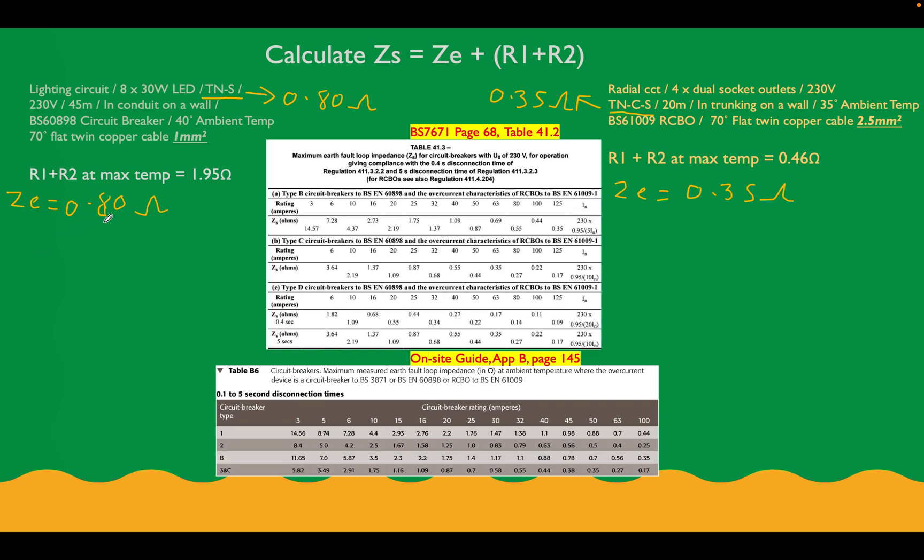So what can we do now? We can add this to our R1, R2 value to get our ZS. So let's put this in, 0.80 plus 1.95 equals 2.75 ohms. So that's our ZS value for this circuit.